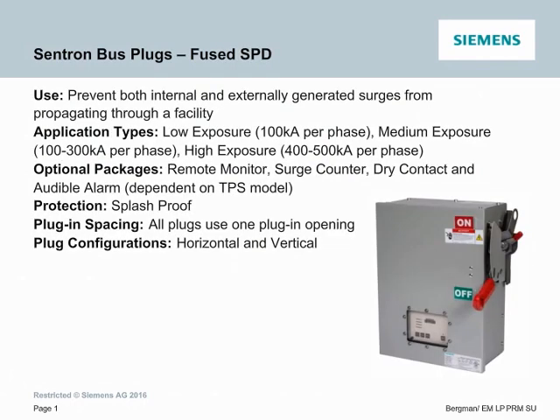On this slide we have the SENTRON bus plugs using the Fused Surge Protection Device, or SPD. The use here is to prevent both internally and externally generated surges from propagating through a facility. For the application types, you have multiple exposure types here. You have your low exposure, medium exposure, and high exposure type applications. We're looking at data centers and hospitals perhaps. Optional packages for the Fused SPD would be a remote monitor, surge counter, dry contact, and an audible alarm. You have splash-proof protection. Once again, all plugs use that one plug-in opening, and you have both the horizontal and vertical configurations.